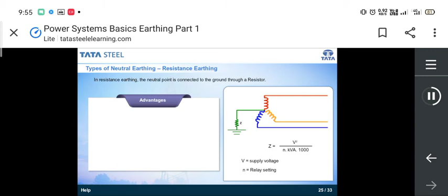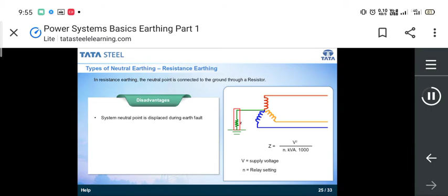In resistance earthing, fault current is reduced. This type of system requires a low rupturing capacity breaker. Let us take a look at the disadvantages now. In this system, the neutral point is displaced during earth fault. The cost of the transformer increases as graded insulation towards neutral cannot be used. Further, provision of a resistor involves extra investment and it requires more maintenance. Let us move on to the next screen.